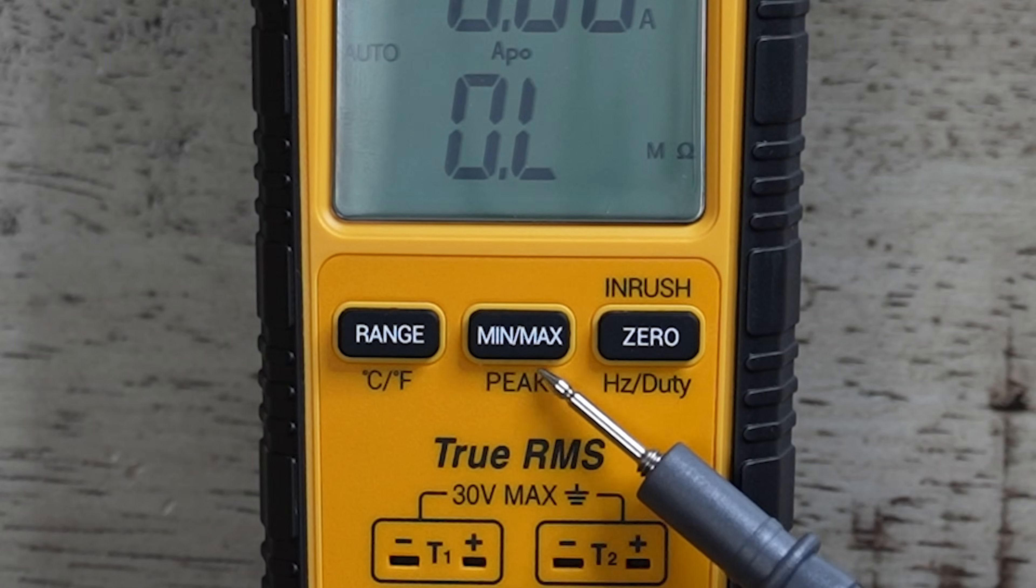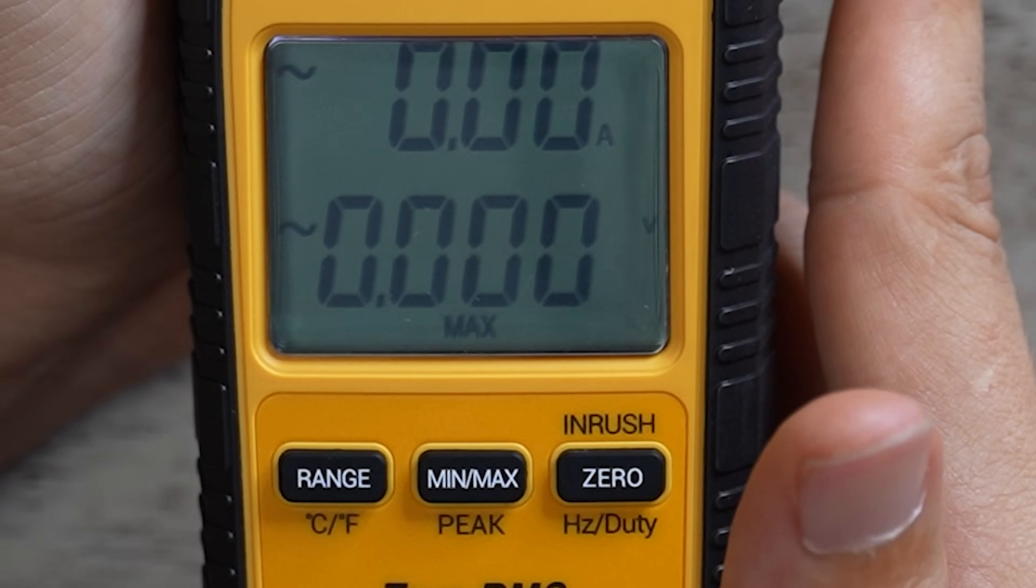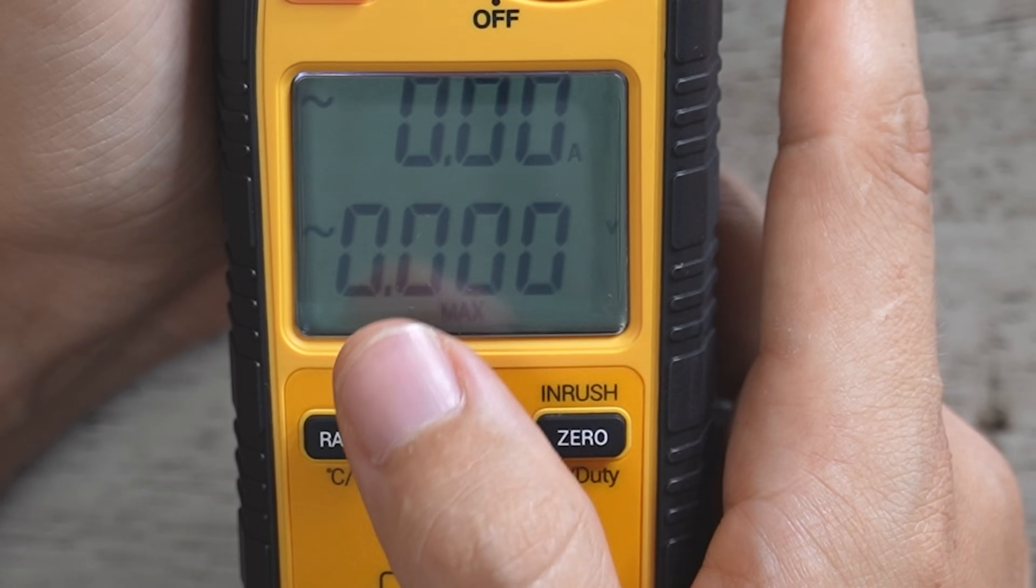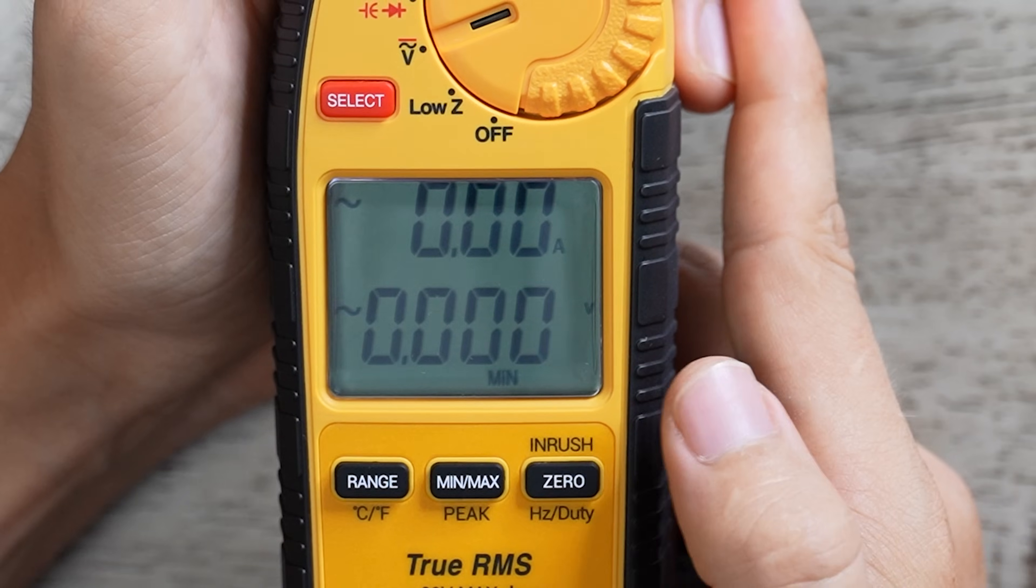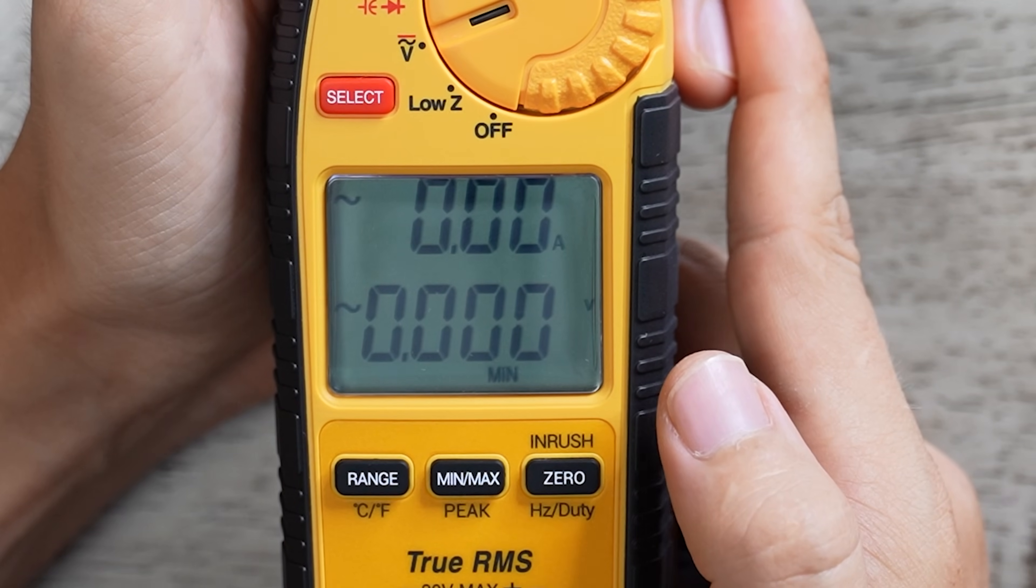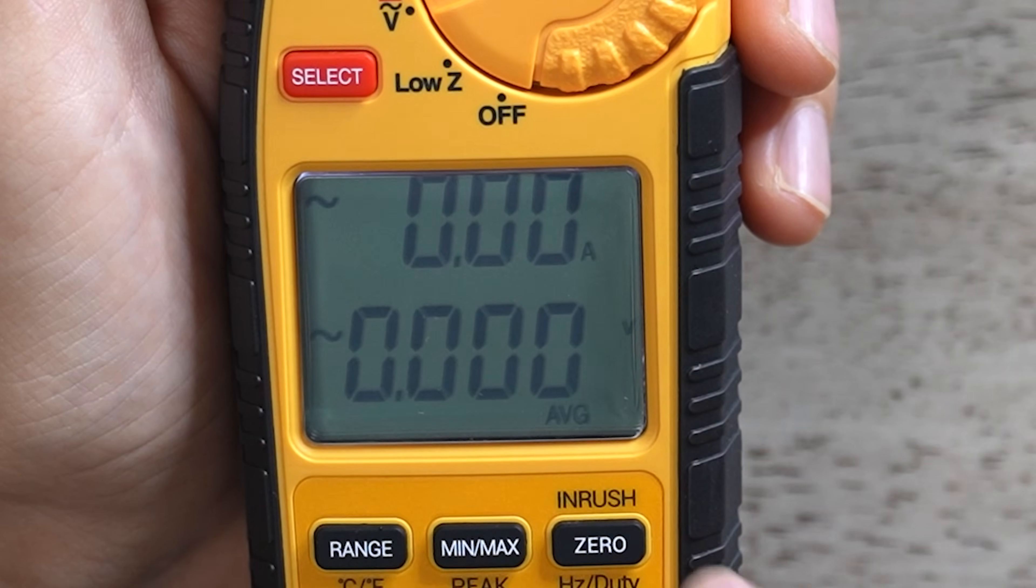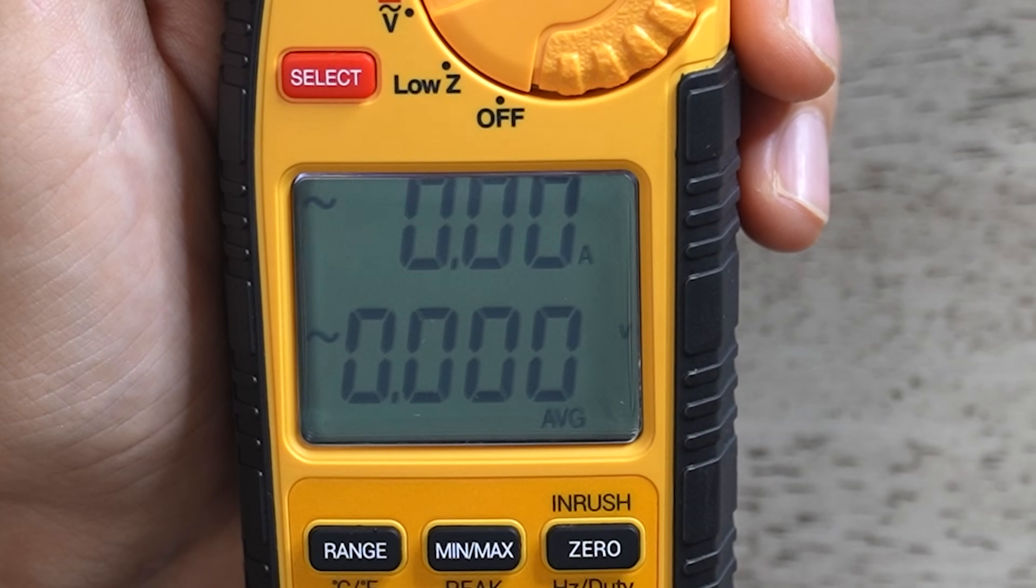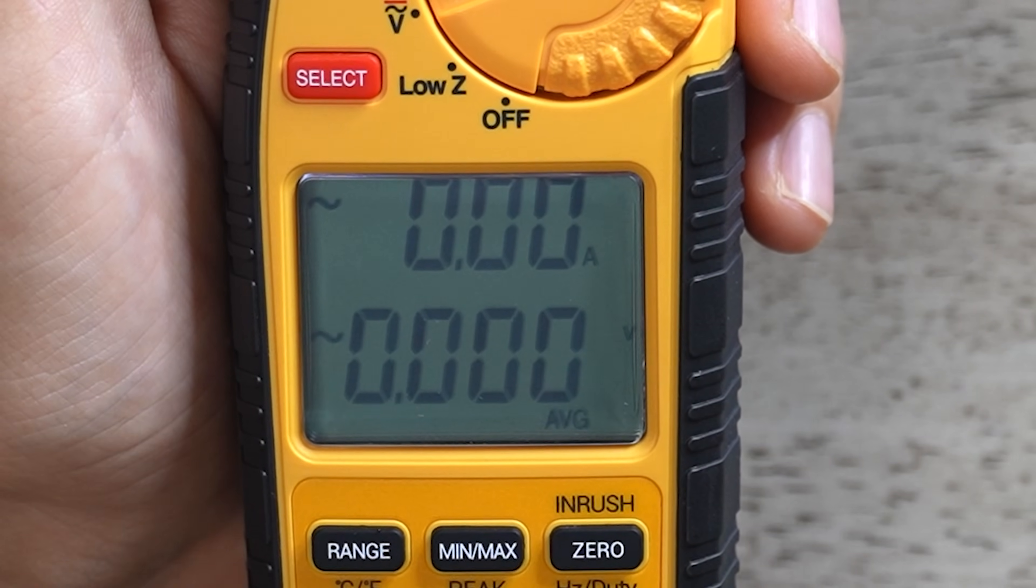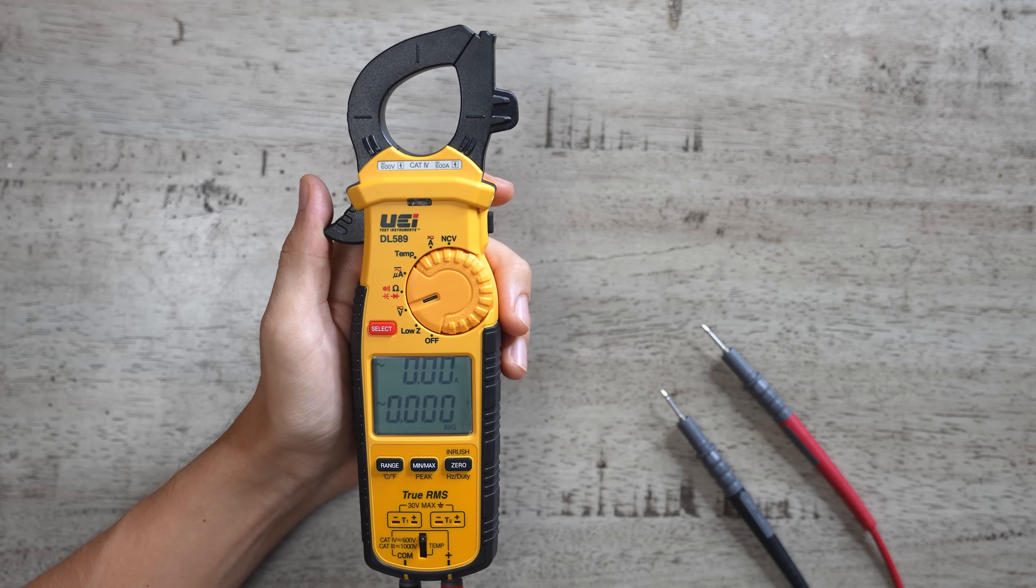Next up, we have the minimum, maximum, average, and peak button. If you select max, while you're measuring voltage, amperage, or resistance, whatever reading that the meter will register that is the highest, that one is the one that's going to stay on the display. Min is the same thing, except it records the lowest reading that the meter registers. And then we have average. If whatever it is that you're measuring is fluctuating, let's say you're measuring an outlet, and the voltage is bouncing around from 115 to 122, the average would simply give you the average read, which would probably be around 117 volts.